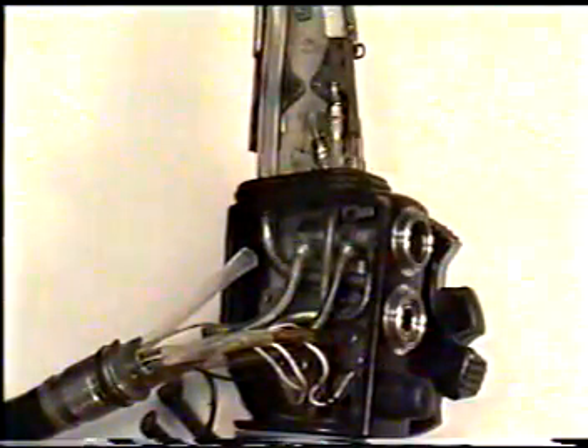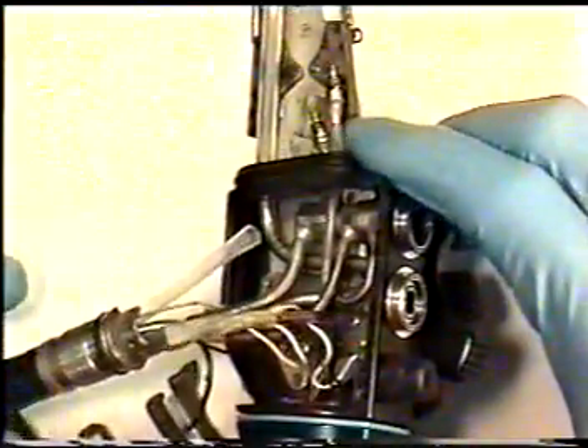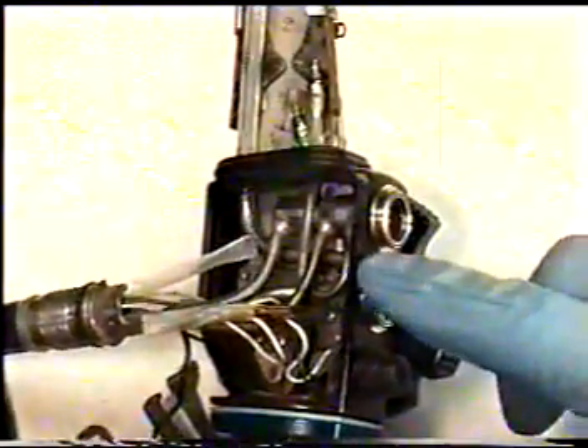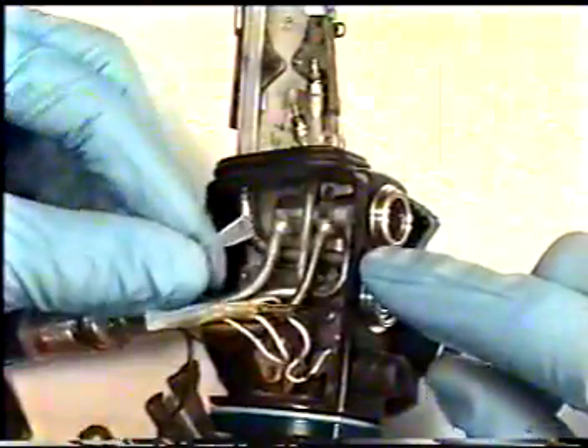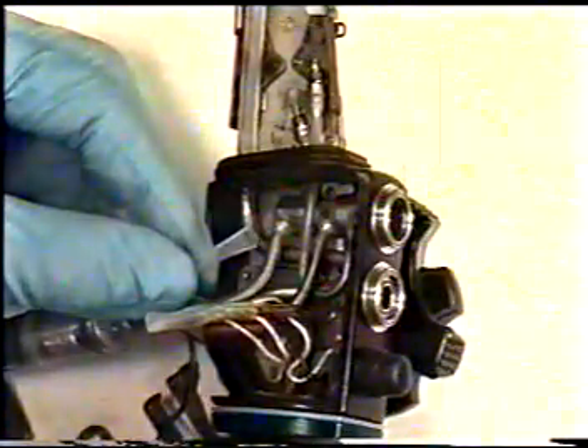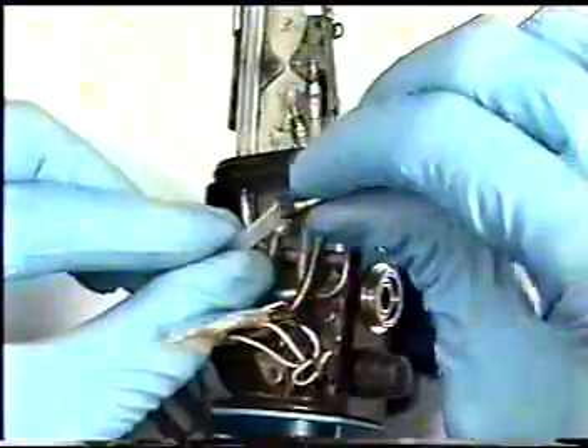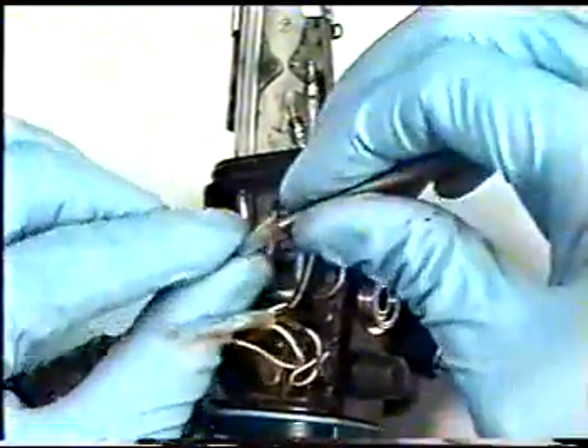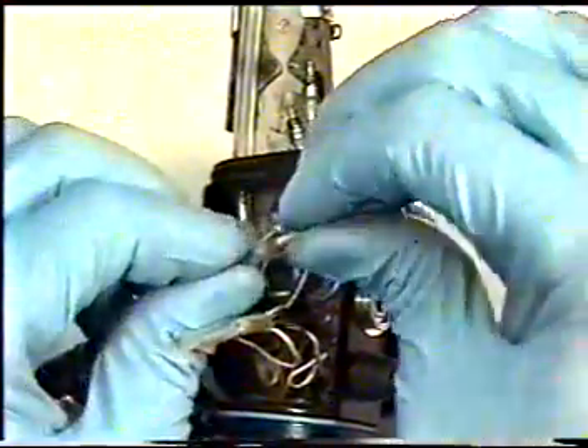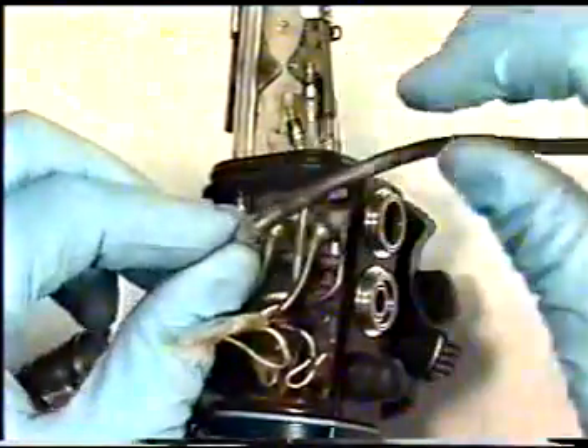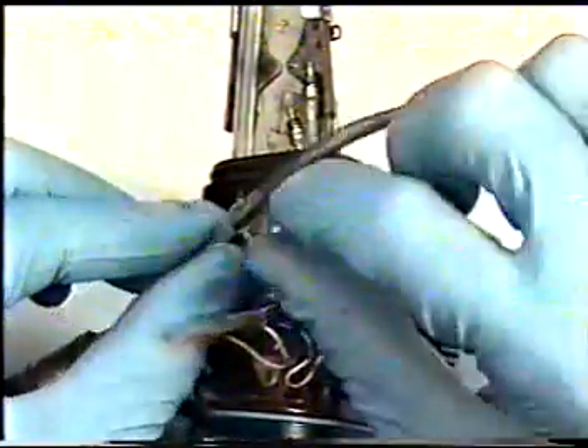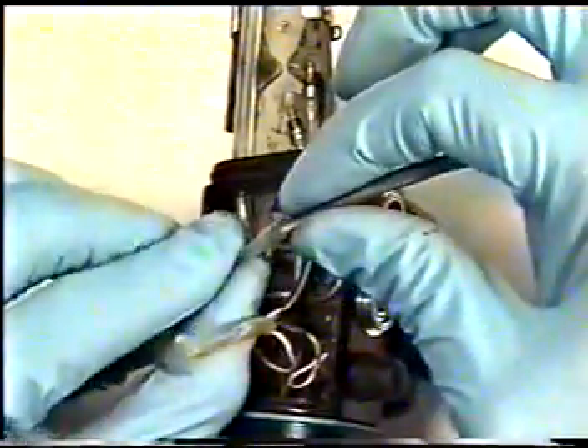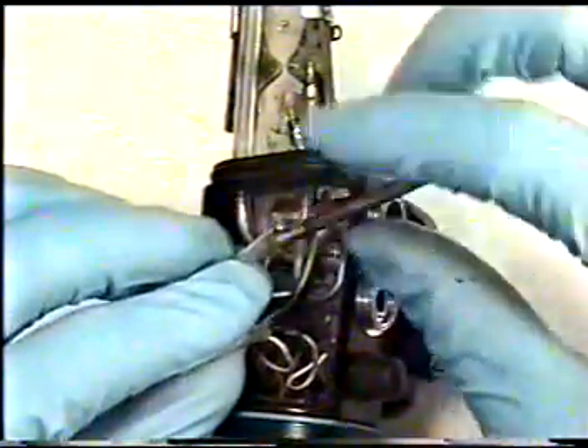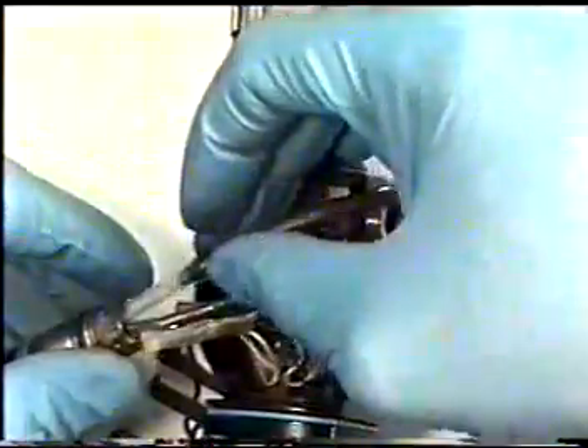Being sure to check the model number of the instrument and purchasing the same exact model number for the Olympus instrument you are repairing. Obtaining your new light guide illumination bundle, we will now reverse the process and reassemble the endoscope with a brand new illumination light guide bundle. Attach your new light guide bundle to your clear plastic tubing, which is oversized to fit over your light guide illumination bundle, and we'll now pass it back through the endoscope light guide umbilical cord section.